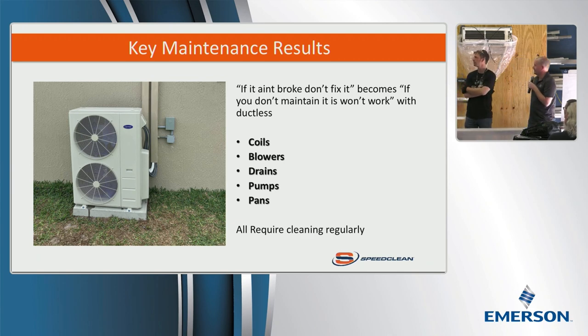If it ain't broke, don't fix it becomes if you don't maintain it, it won't work with ductless. I understand if you're out west, like Utah, it's not going to be nearly as bad, which is why VRF and VRV are really popular in arid climates where drains backing up isn't as big a deal and maintenance isn't as big a deal. In markets with high moisture content, stuff grows more. So you have to consider your market before selecting equipment. VRF, VRV is excellent technology, it works great, but it has to be designed for, and maintenance has to be planned for.